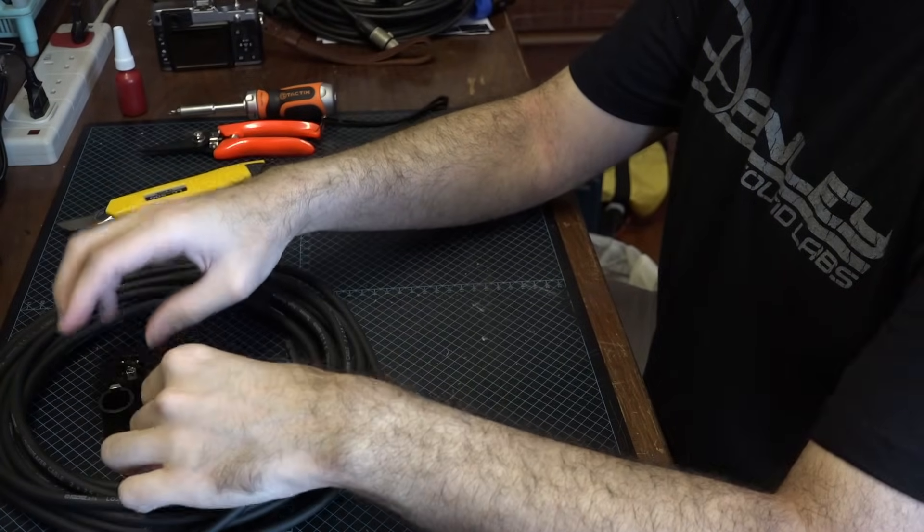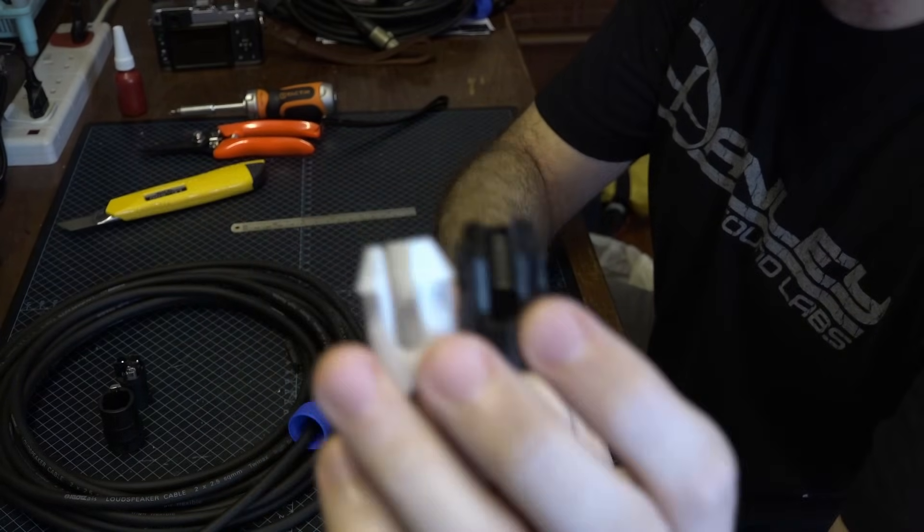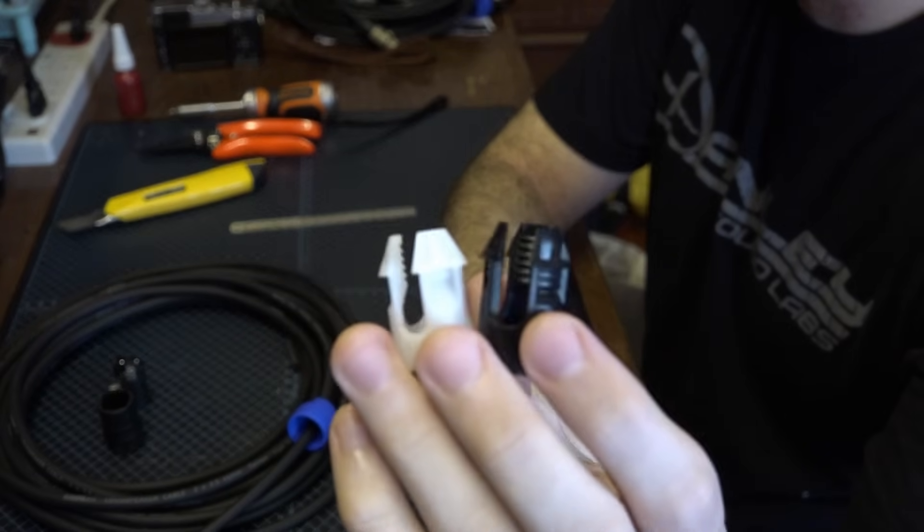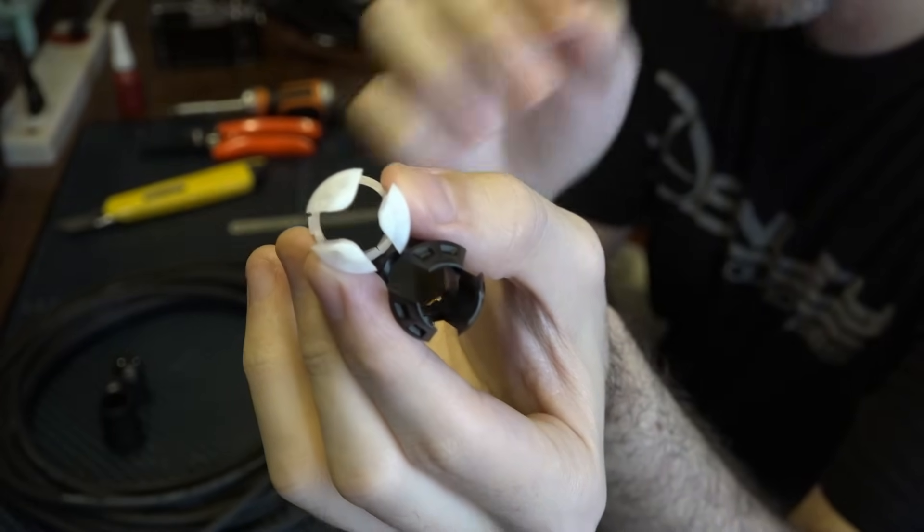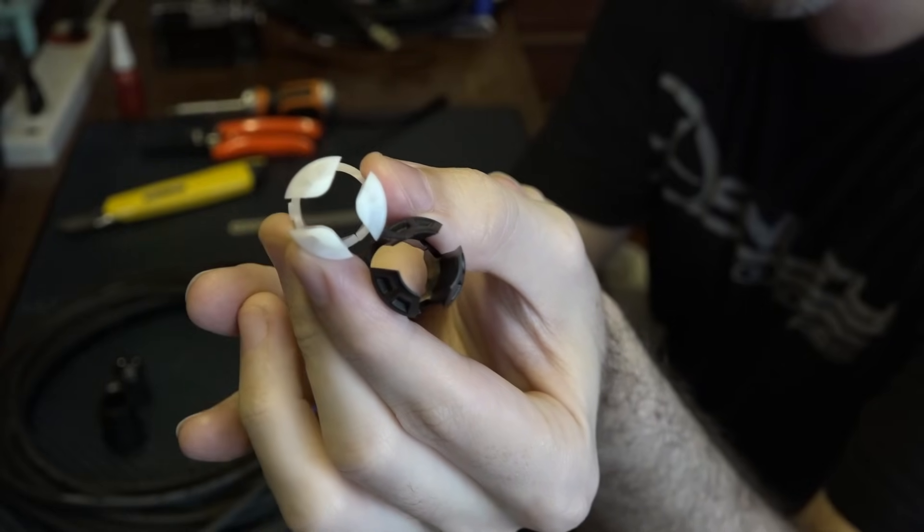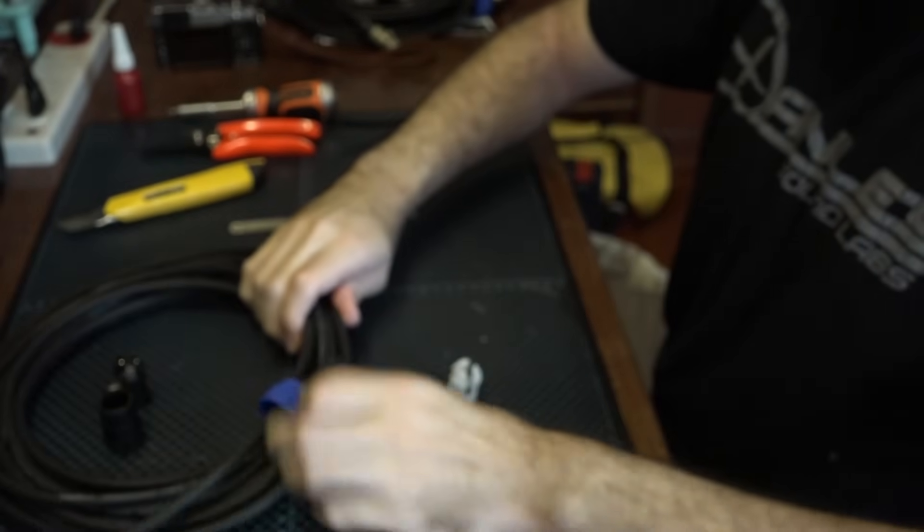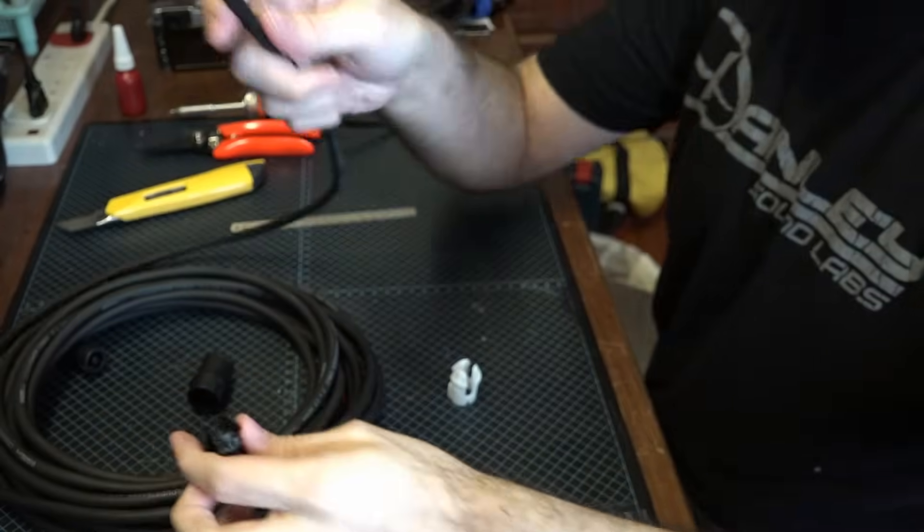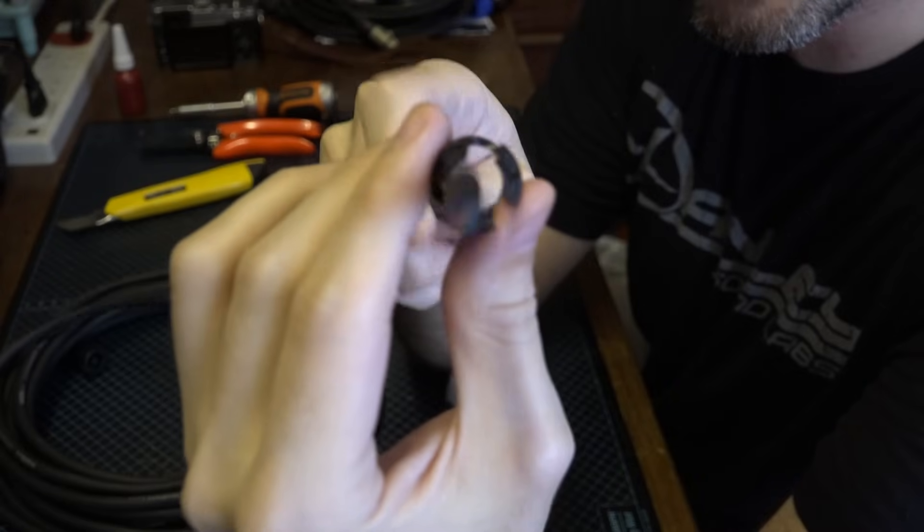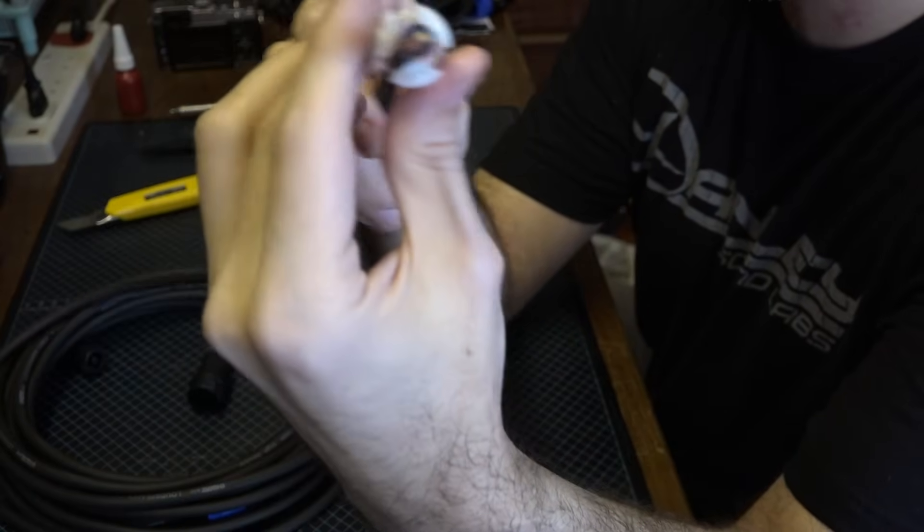You will also be given two strain reliefs. So you'll have a white strain relief and you'll have a black strain relief. The difference between them is the diameter. The white strain relief is for smaller cabling and the black strain relief is for larger cabling. Exactly which one you use depends on the thickness of your cable. The way that you check is you take your cable and you feed it into the strain relief. Now as you can see there with a black strain relief there's a huge amount of space. So that's not the right one for this application. The white one on the other hand there's just a small amount of space so we'll use that.